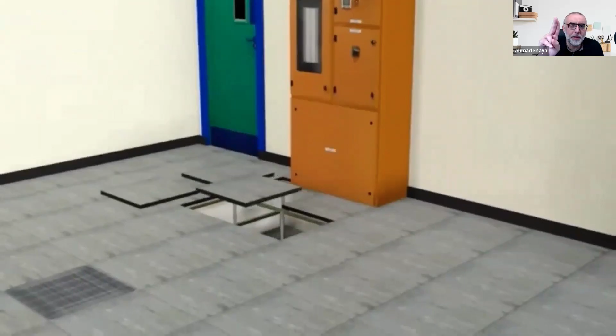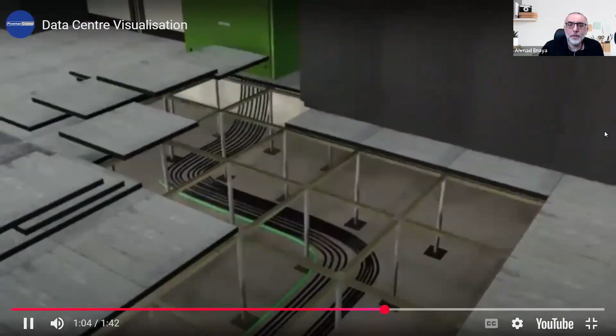We should have two power supplies - one of them is the brown one here, one is the green. We should have two power sources, so maybe one comes from a certain utility company; that's the first power source. Every cabinet, every rack should have two power outlets, two power distribution units - one power coming from the green side, one from the brown side, and both connect to the rack. So the rack has two power supplies, one from brown, one from green, and every component inside the rack should be connected to both. Even if a component has four power supplies, two connect to the brown and two to the green. It's much easier and cleaner when we have a raised floor.